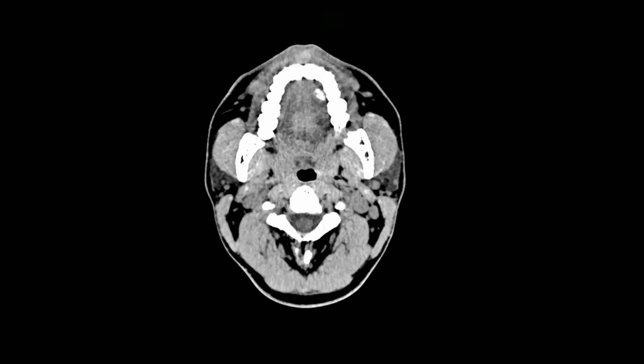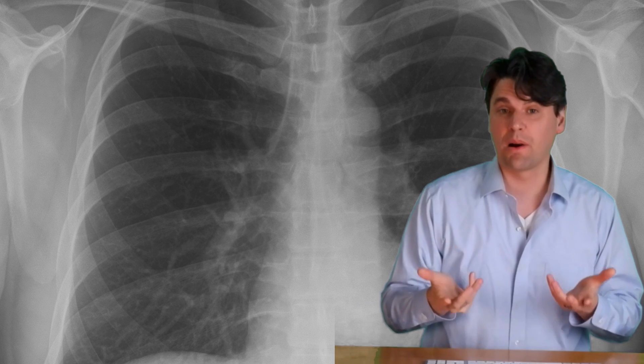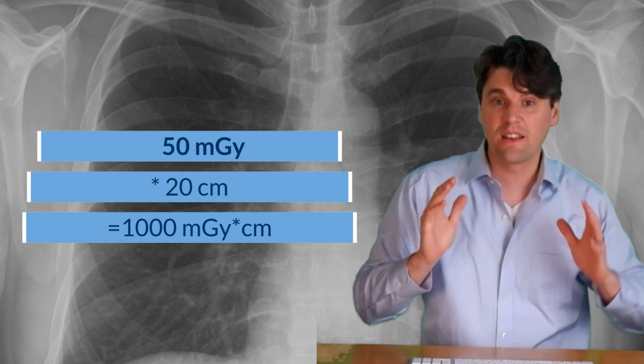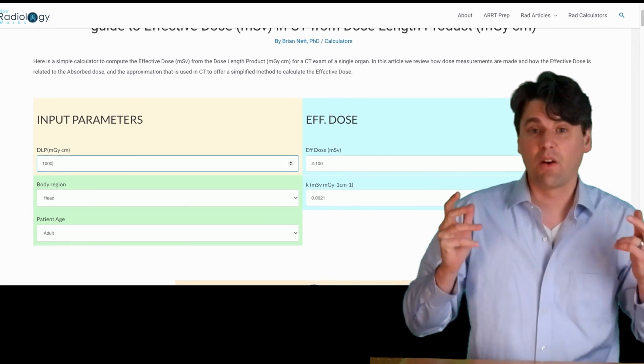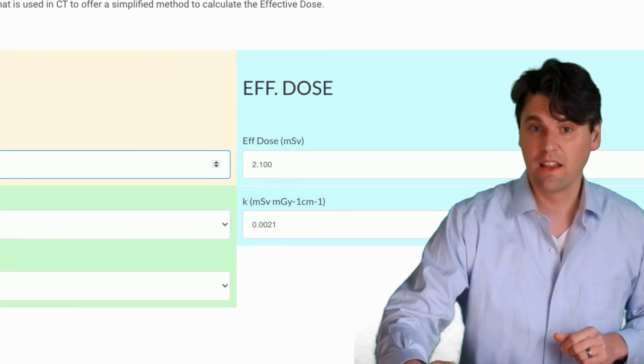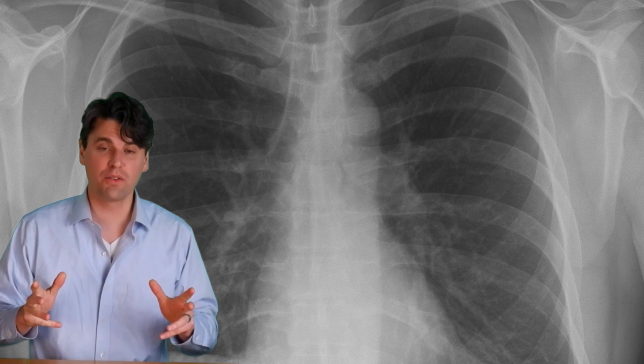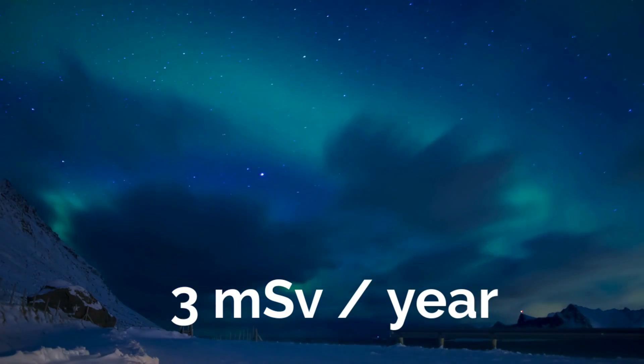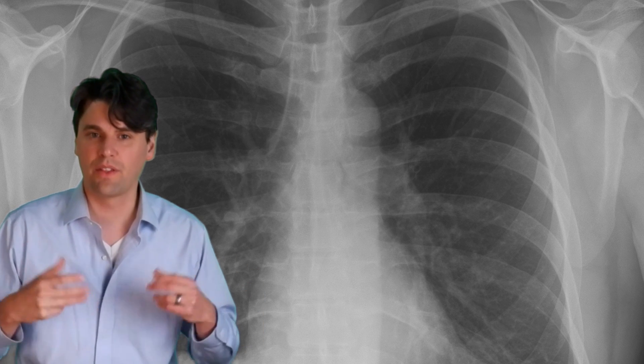The first example we're going to do is a routine brain CT. Imagine an adult comes in — a routine brain CT representative dose could be about 50 milligray, and for round numbers let's say the distance is 20 centimeters. So the DLP that the system is going to report is going to be 1000 milligray centimeters. With 1000 milligray centimeters and an adult with the area of interest as the head, you can see that the effective dose is around two millisieverts. To put that in context, three millisieverts is the background radiation on average you'll get in the United States, so a non-contrast CT represents about two thirds of background radiation.